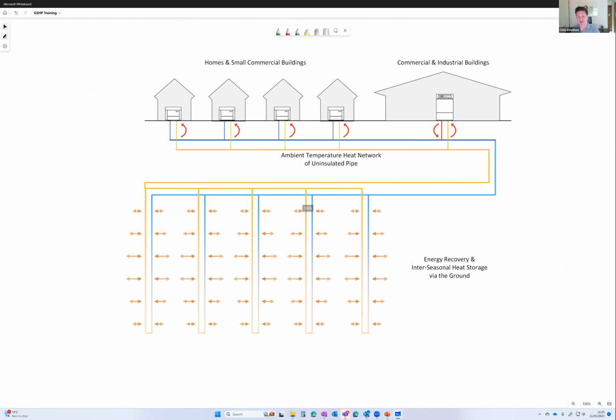This is a good example of that. We've got a mix of maybe small commercial and larger industrial commercial buildings on a single ground loop. Let's say this is a supermarket putting heat into the ground, and we maybe have some dwellings taking heat out of it as well. So the more diverse loads we mix on these networks, the more effective and efficient they become. You might even need less loop to do the same load because you're putting something back in.